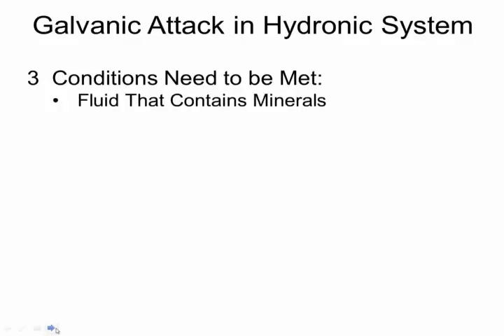Well, first of all, you need to have fluid that contains minerals. If your fluid doesn't contain minerals, you don't have an issue. And perhaps the water fill for your hydronic system is going to be taken from a source that is largely surface water, as an example, and that might be without minerals. I grew up near Detroit, and our water was taken from the Great Lakes. As a kid, it was great tasting water. I mean, it had a lot of chlorine in it. I go back there and taste it now. It's not so good. I have to have probably a beer chaser to tolerate it, but basically it was soft water, naturally soft water. So anyway, one of the conditions is fluid that contains minerals.